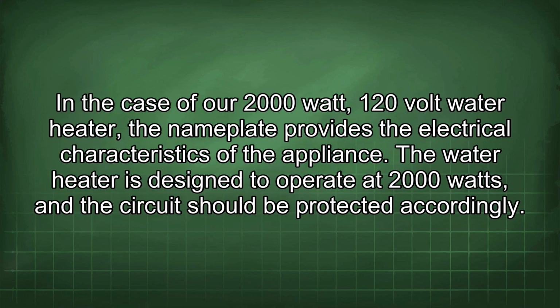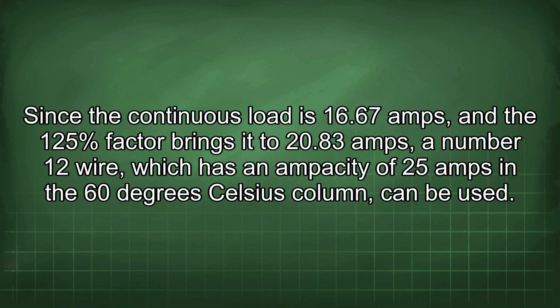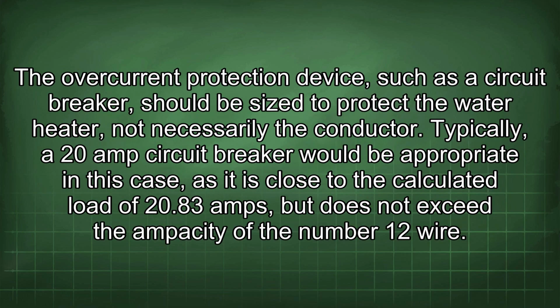In the case of our 2000-watt, 120-volt water heater, the nameplate provides the electrical characteristics of the appliance. The water heater is designed to operate at 2000 watts and the circuit should be protected accordingly. Since the continuous load is 16.67 amps, and the 125% factor brings it to 20.83 amps, a number 12 wire, which has an ampacity of 25 amps in the 60 degrees Celsius column, can be used. The overcurrent protection device, such as a circuit breaker, should be sized to protect the water heater, not necessarily the conductor. Typically, a 20 amp circuit breaker would be appropriate in this case, as it is close to the calculated load of 20.83 amps but does not exceed the ampacity of the number 12 wire.